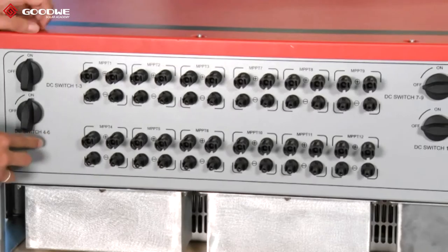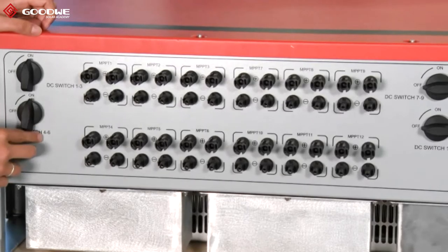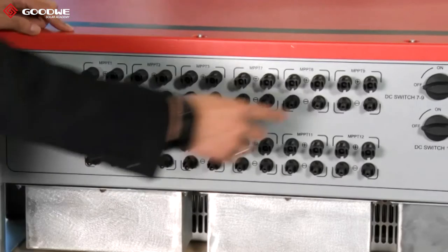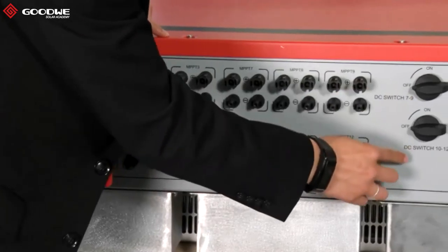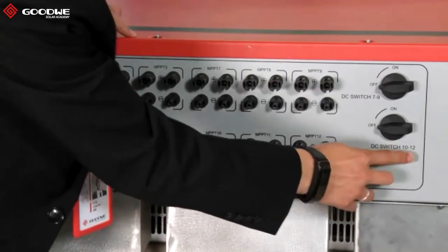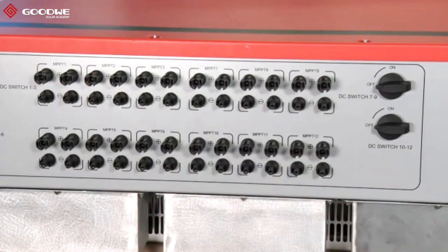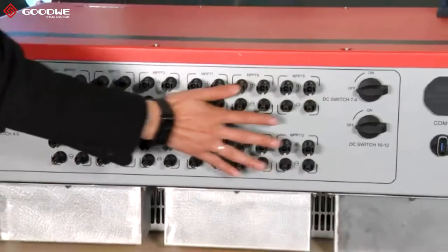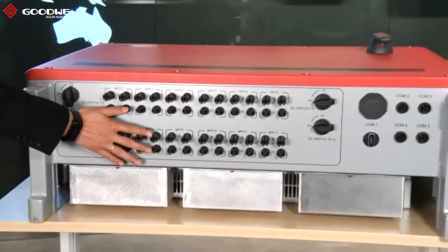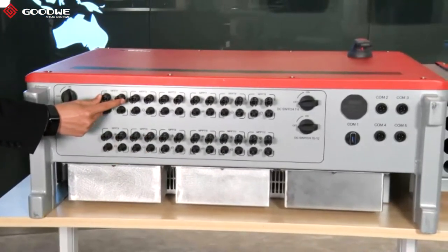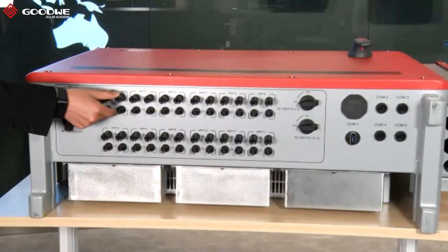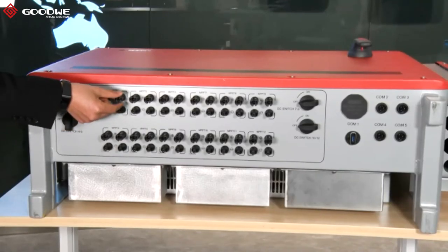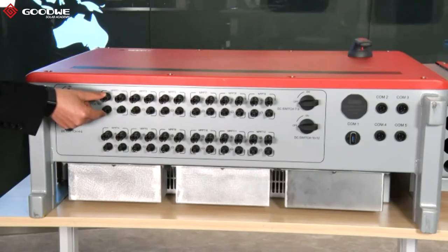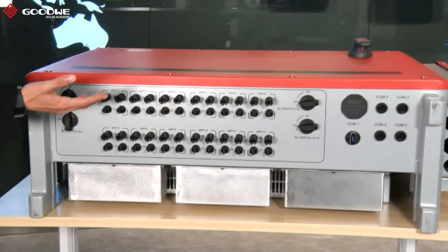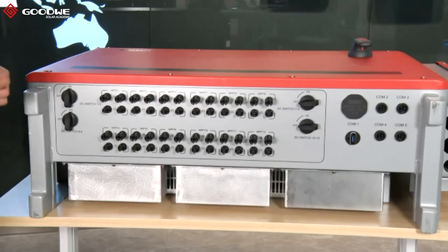And this switch is for 4 to 6, this one is for 7 to 9, and this one is for 10 to 12. For the DC switches, we have 12 MPPT trackers in total. For each MPPT tracker, we have 2 DC inputs, which means you can connect 2 strings for each MPPT tracker.